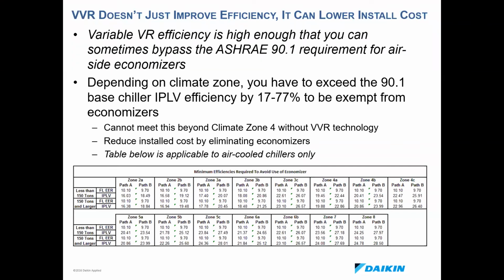The reason why it's important is not only the efficiency benefits, but it'll also help you exceed the requirements that ASHRAE 90.1 has for airside economizers. So 90.1 has these efficiencies listed that you need to meet to avoid the use of an economizer. And depending on where you are, which climate zone, you have to beat this base efficiency by 17 to 77% to be exempt from the economizer.